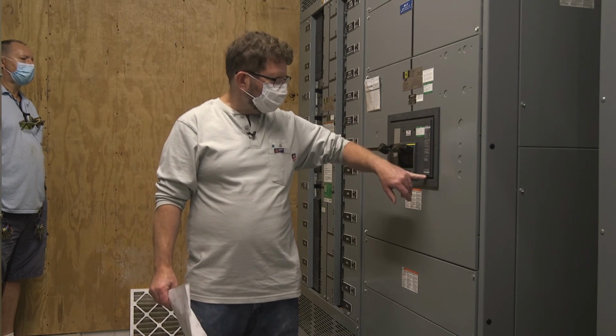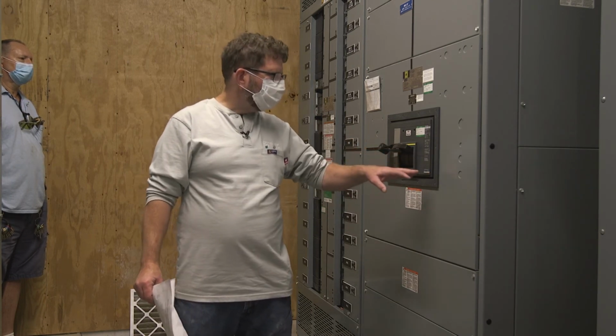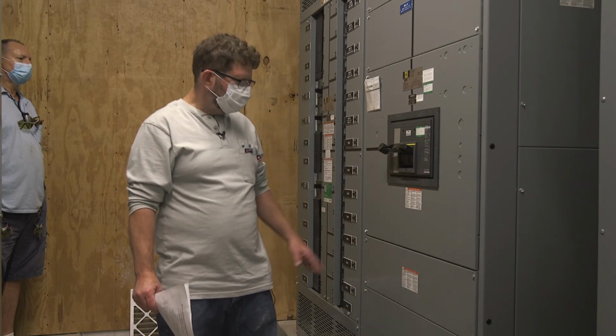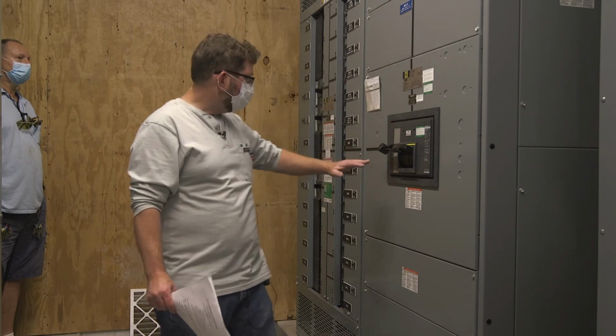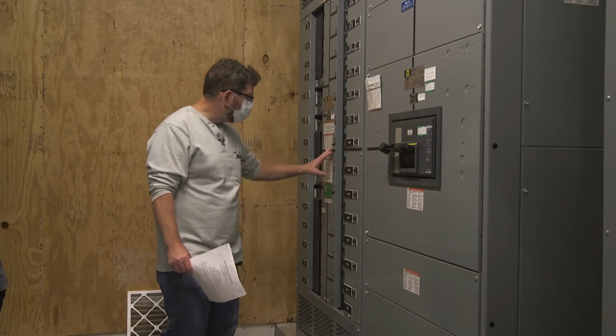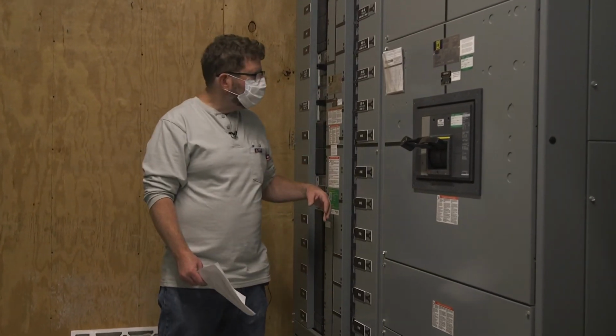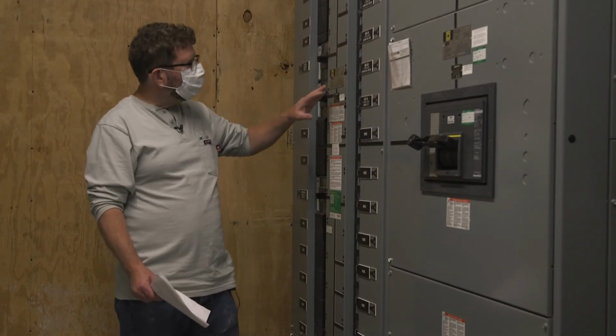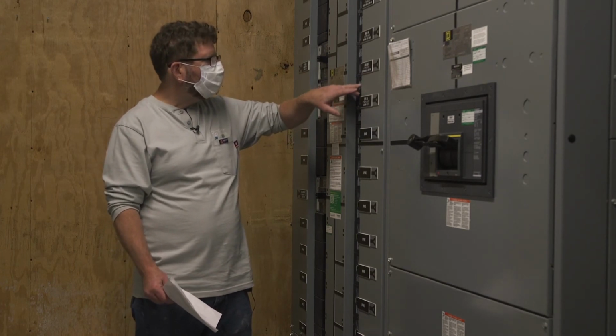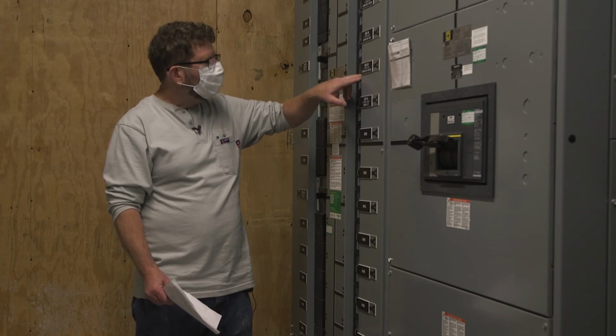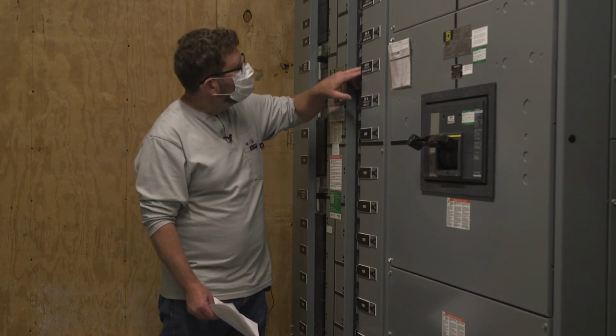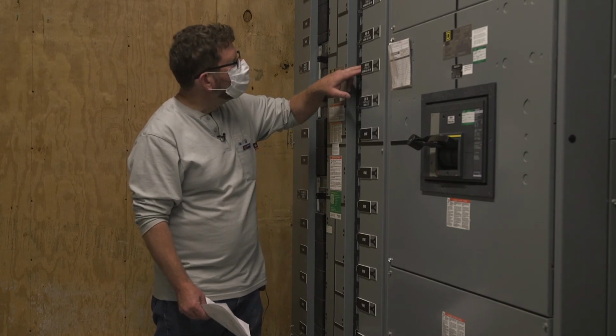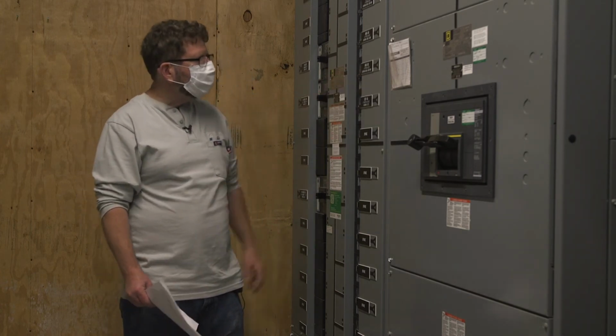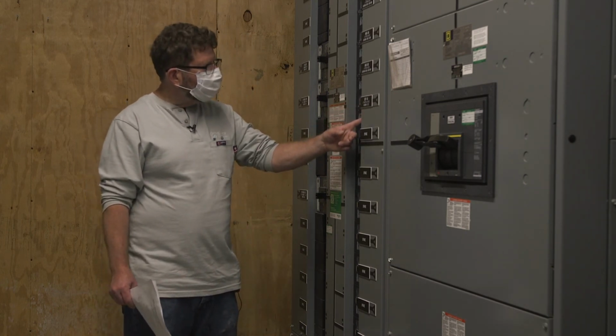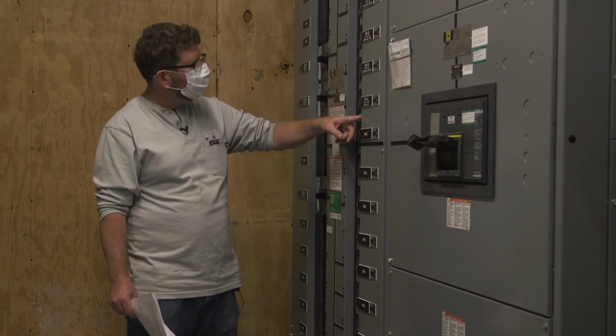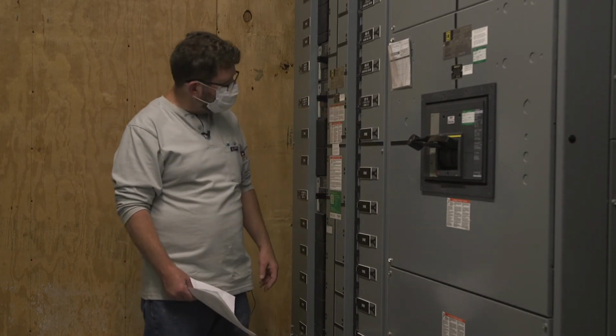Nameplate, just like the other ones, date code, like all other Square D equipment. It's not a draw-out breaker, it's just bolted in. This is our I-Line switchgear, or I-Line distribution panel. We have a bunch of little breakers and a couple of larger frame breakers. These all have the nameplate with all the rating information, serial number and date code. It's made in 2018, week 23, day 2. You have the little red button to exercise it. You do have some trip settings here on these. Some of these have trip units, some of them are just thermal mag breakers.